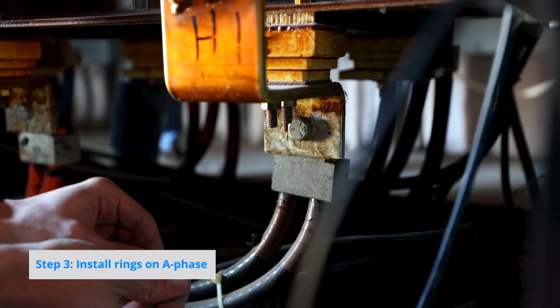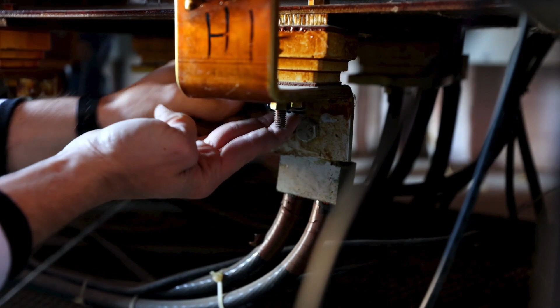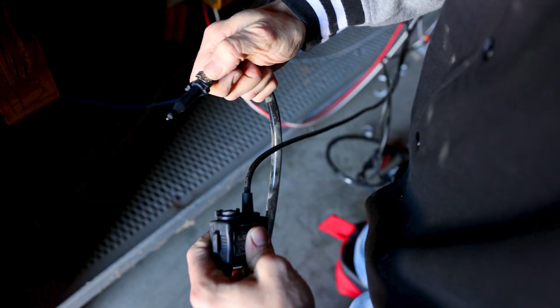And last for the voltage rings here, we have A-phase on H1. It is black in color, and so we're placing the ring on the lug and then lock washer and nut so it also doesn't come off. So next we're putting on our CT coils.